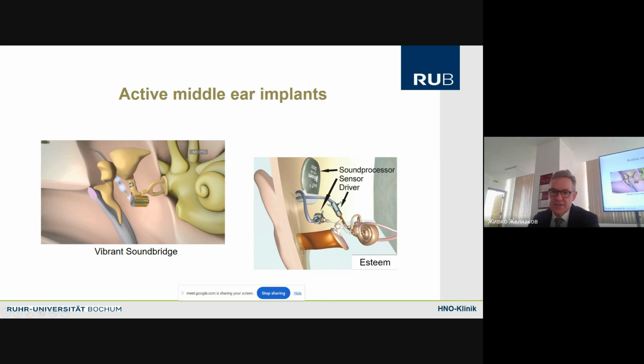Here we have the sensor system, which gives the information to the processor. The processor can be programmed according to the patient's hearing situation. And then the electrical signal is given to the driver, the actuator, which is coupled to the stapes. The problem in this system is that we have to interrupt the ossicular chain, because the sensor is coupled here and the driver is coupled to the stapes. The incus needs to be removed. So if the system is off, the patient has a conductive hearing block of about 60 dB. So he's only able to hear when the system is on.